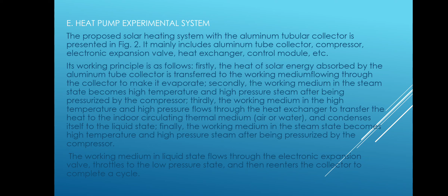Secondly, the working medium in the steam state becomes high temperature and high pressure steam after being pressurized by the compressor. Thirdly, the working medium in the high temperature and high pressure state flows through the heat exchanger to transfer heat to the indoor circulating thermal medium and condense itself to the liquid state. Finally, the working medium in liquid state flows through the electronic expansion valve, throttles to the low pressure state, and then returns to the collector, completing a cycle.